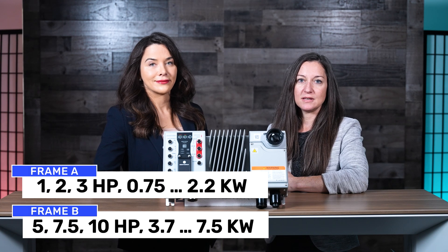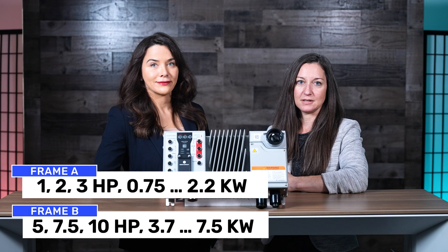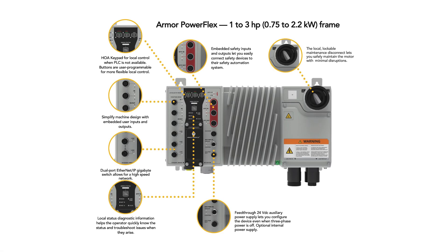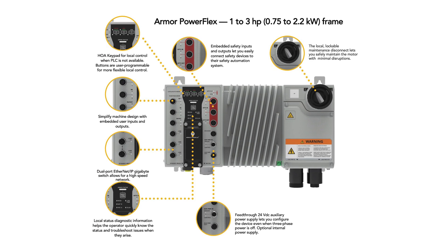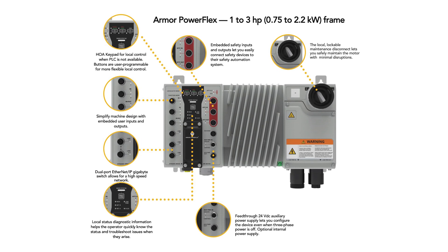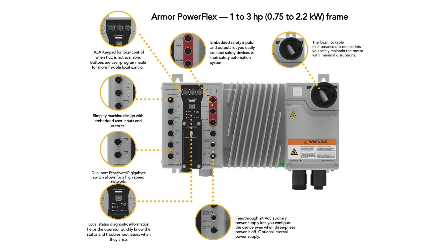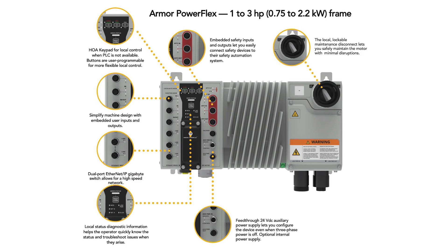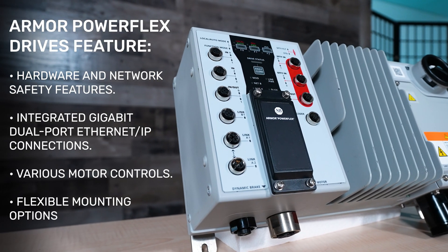The drive enclosure has an IP66 Type 4/12 environmental rating. Internal 24VDC control power options are available. Armor PowerFlex natively supports Ethernet IP at 1 gigabit speed using an embedded dual port switch that supports device-level rings. It also comes equipped with onboard digital and safety I/O, a local disconnect, and motor control options. It supports open and closed-loop speed control for maximum application flexibility.